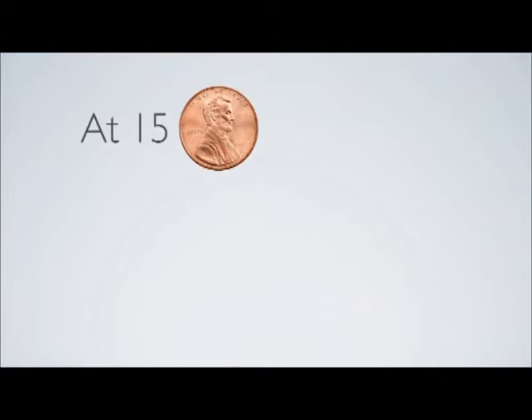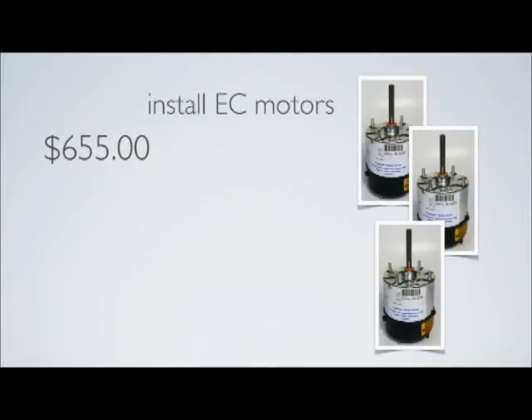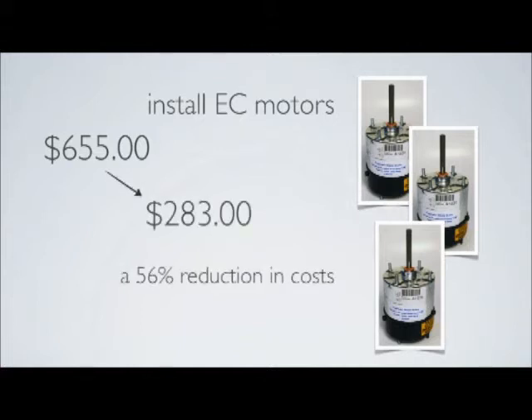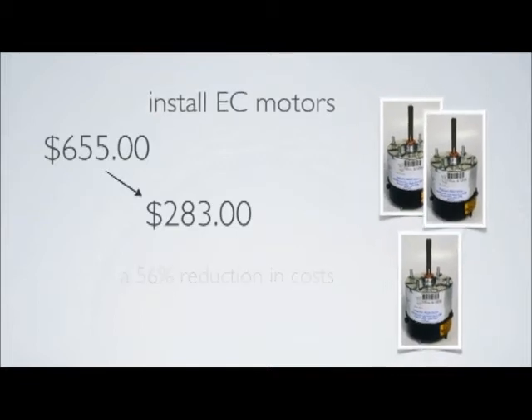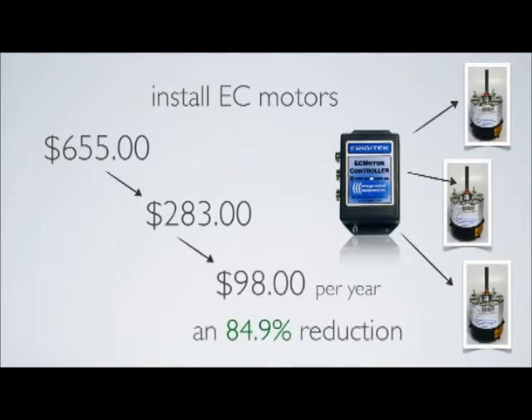At a price of 15 cents per kilowatt hour, it will cost $655 to operate an evaporator coil with 3 conventional fan motors each year. By installing EC motors, the cost to operate the fans is lowered to $283 — a 56% reduction in costs. However, by installing a FrigiTEN EC controller, the cost to operate the fan motors is reduced to $98 per year, an 84.9% reduction. There is no other single product on the market that can produce this kind of combined savings in a commercial refrigerator.